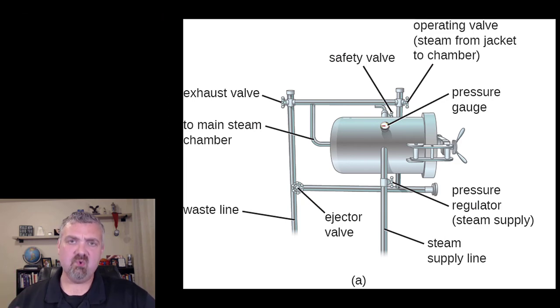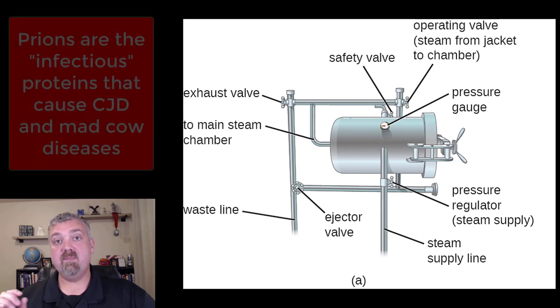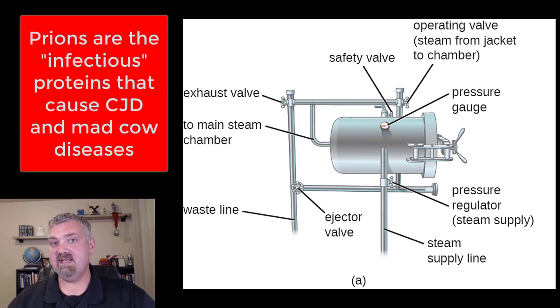So one exception to this rule of 121 degrees. We keep saying that the autoclave sterilizes and I think that's a fair word. But this autoclave, the way that we use it, would not destroy prions - infectious proteins that lead to things like mad cow disease, Creutzfeldt-Jakob disease, etc.